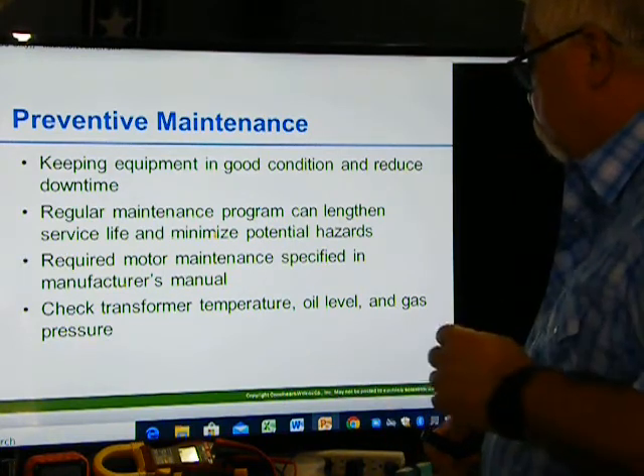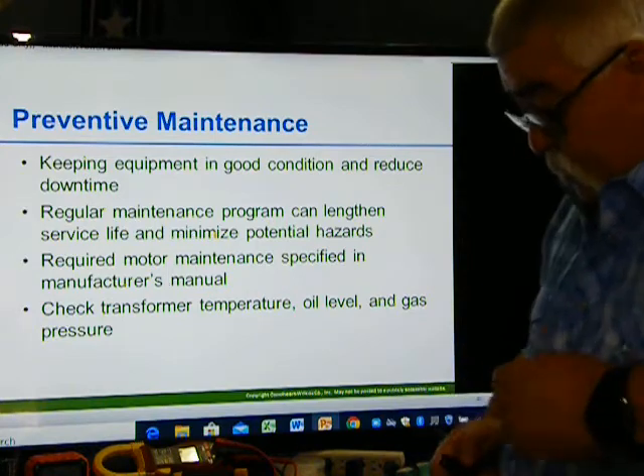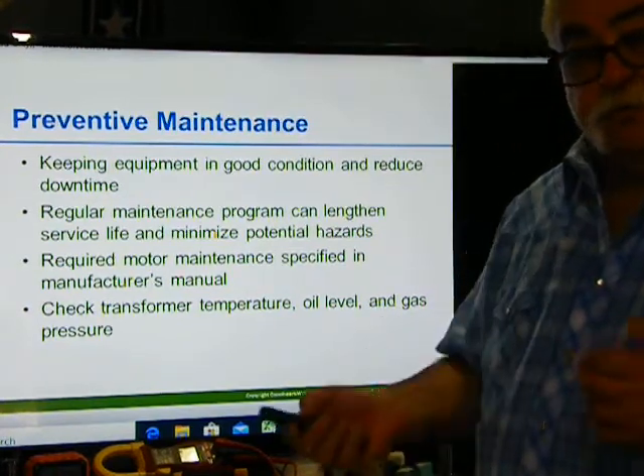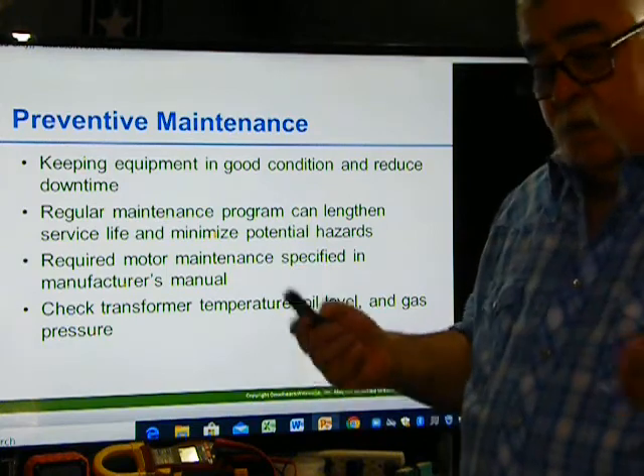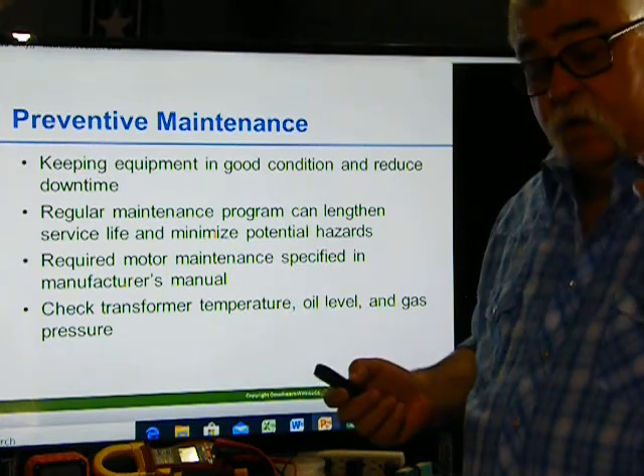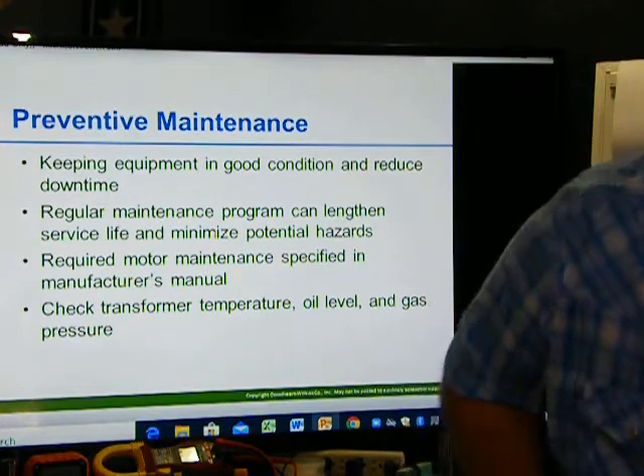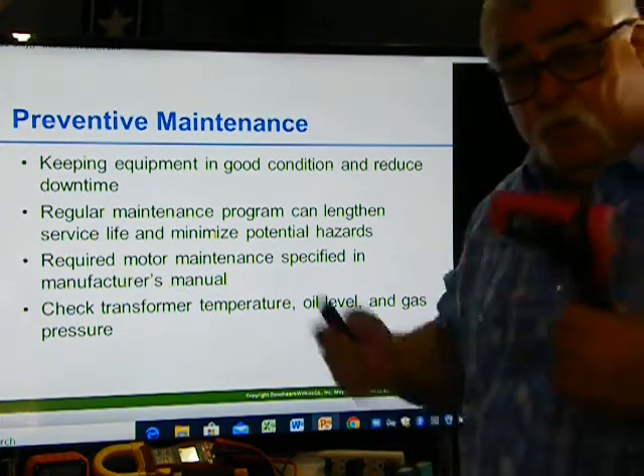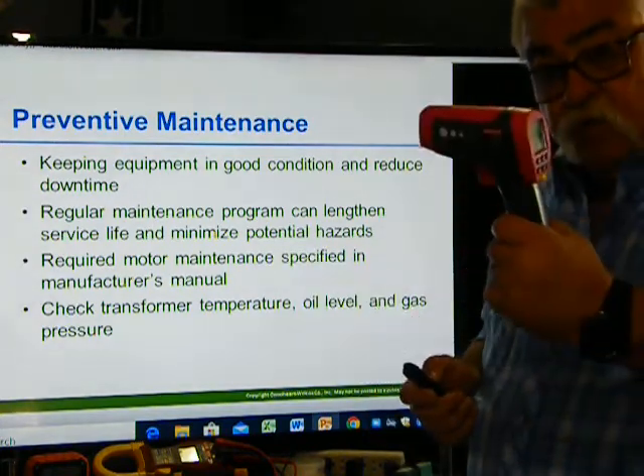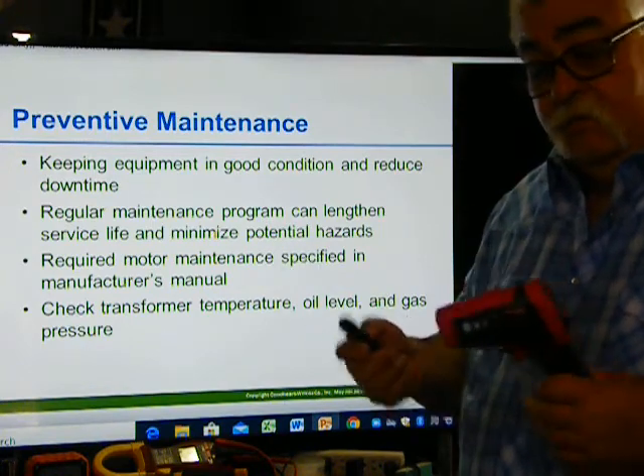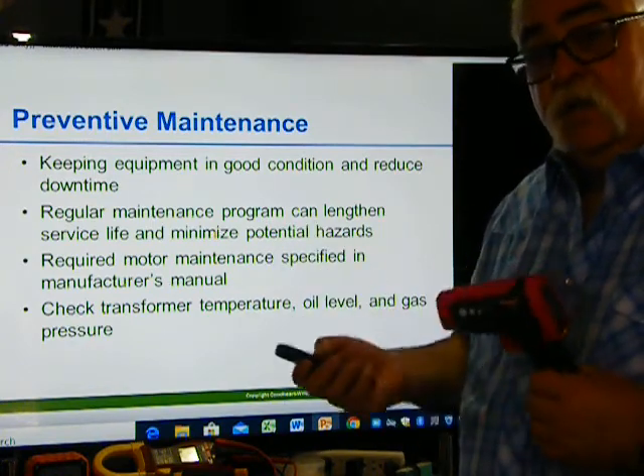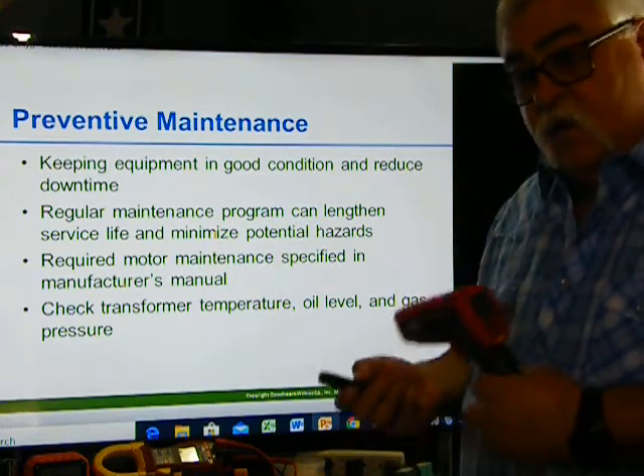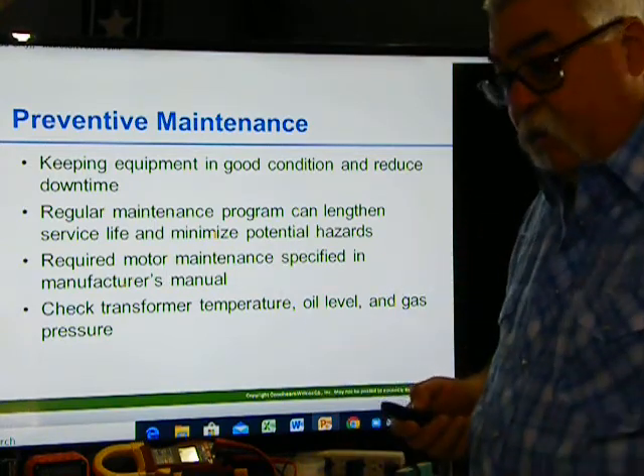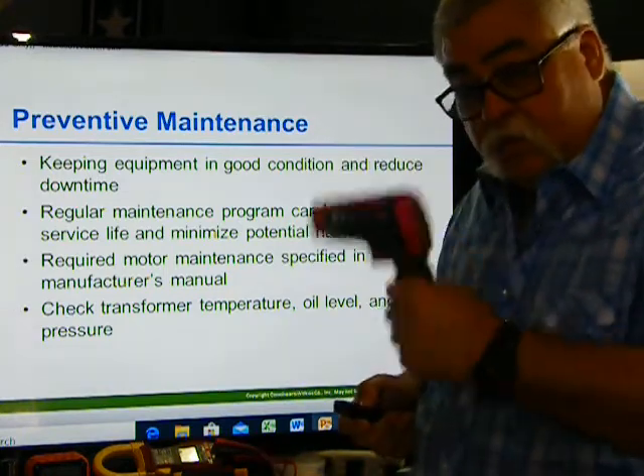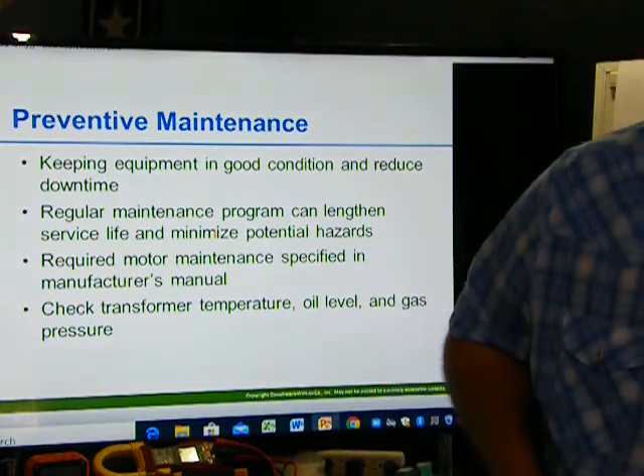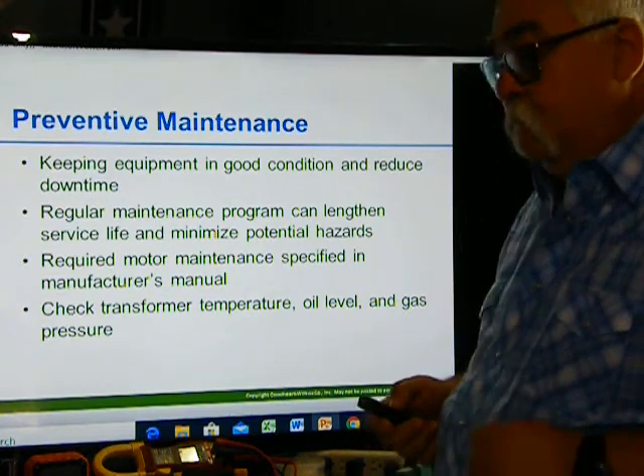Transformers. Check transformer temperature, oil level, and gas pressure. Okay, for most transformers, there's the dry type. If you're using a big transformer to feed a big load, we need to make sure that we check the oil levels. It would be wise to check temperatures when you have your highest load of the day. Make sure that if it has fins on it, it's not exceeding a certain temperature, because heat can cause your transformer to fail also. So we need to check temperature, and make sure the oil is at the level it needs to be.